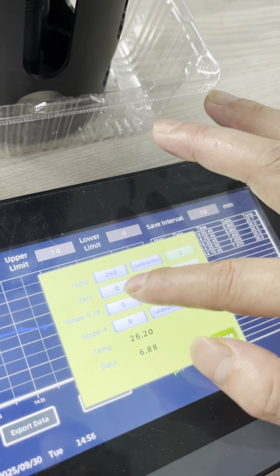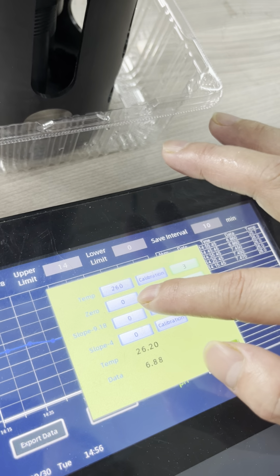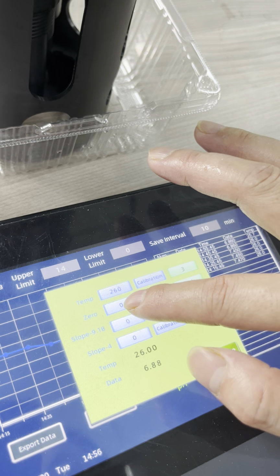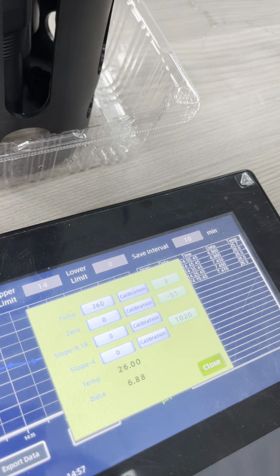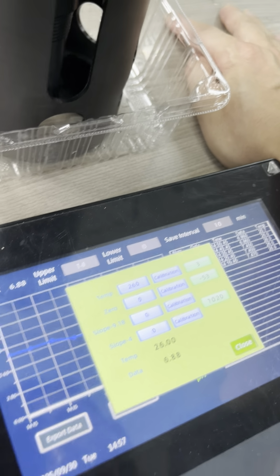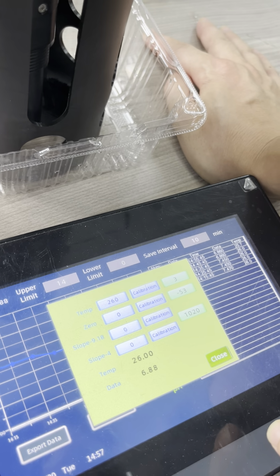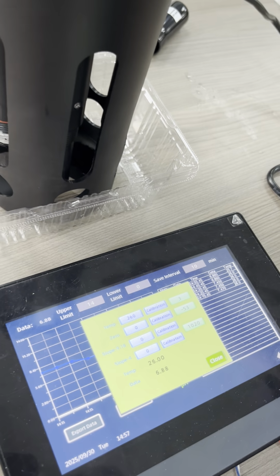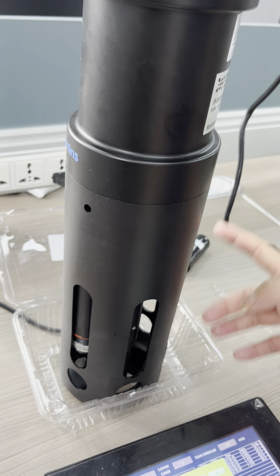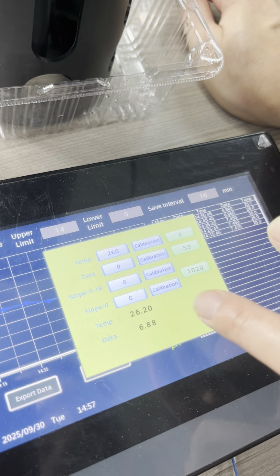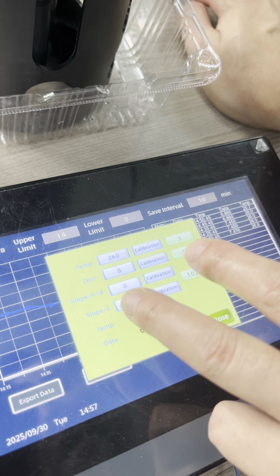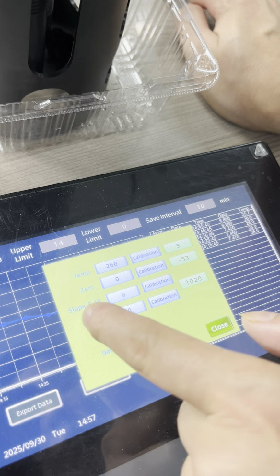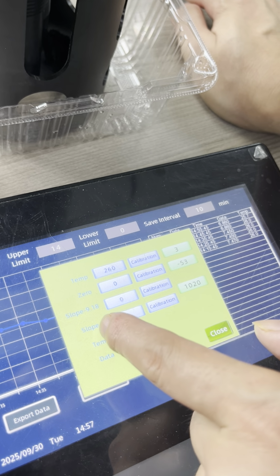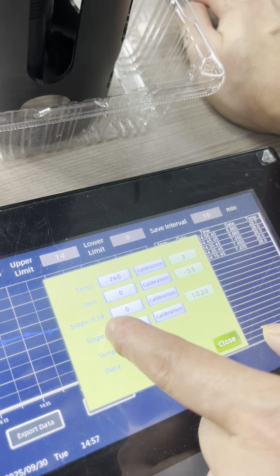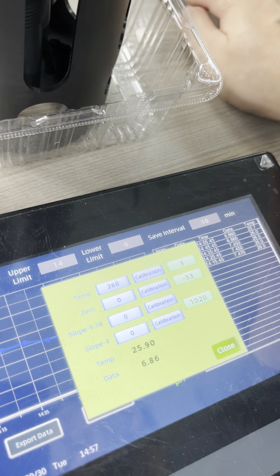Then you click. There's no need to input anything. You do not have to put anything into here. Just click calibration. Then zero calibration is done. Now we will do the slope calibration. We first put the sensor into the standard solution. If the sensor is used in an alkaline environment, we use 9.18 to do the slope calibration.